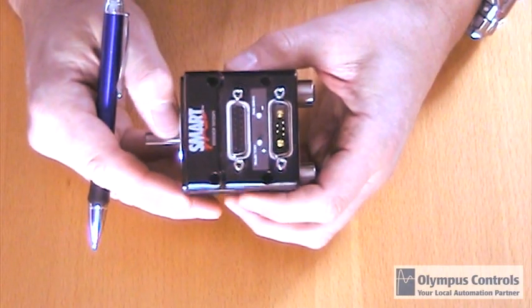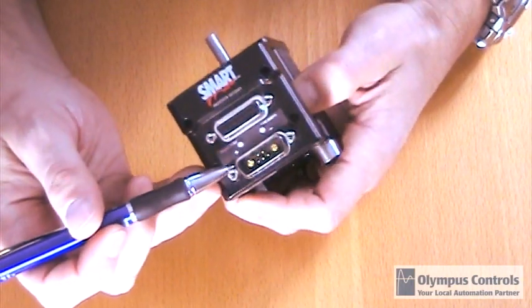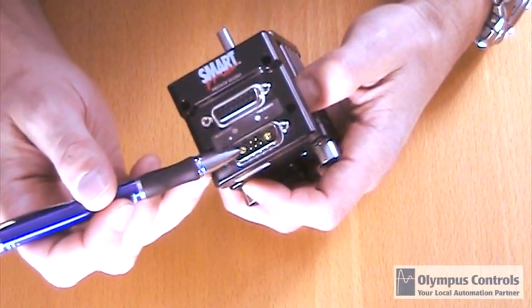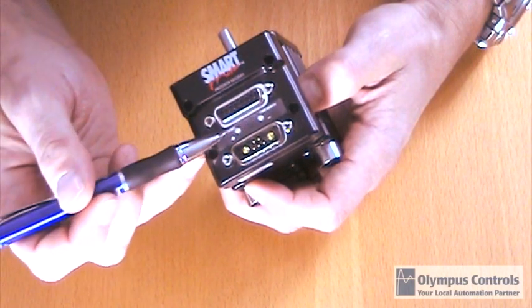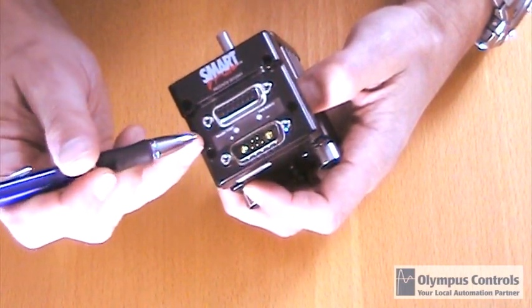So there's a quick peek at a conventional versus smart motor system. Now let's take a little bit closer look at an Animatics Smart Motor. You'll notice two D-sub connectors on the top and a couple of LEDs. The first D-sub connector is where you wire in your 24-volt to 48-volt DC power supply. Additionally, you get a 5-volt trigger and RS-232. You additionally get two status LEDs, one being power and the second being trajectory. Basically, you're going to get green light good, red light bad, and blinking lights in between for troubleshooting purposes.